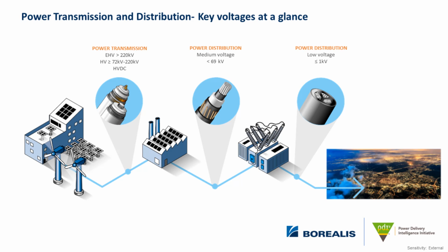And David, how do you like to define high voltage transmission? Would you say that's like 115 kV class and above? Yeah, so a good question. Generally, as a rule of thumb, we consider high voltage 69 kV through 138 kV, and then extra high voltage 230 kV and above. Okay. And then medium voltage would be 15 through 46 kV. And generally, the industry standards and some of the requirements, testing requirements, follow those general voltage classifications as well.